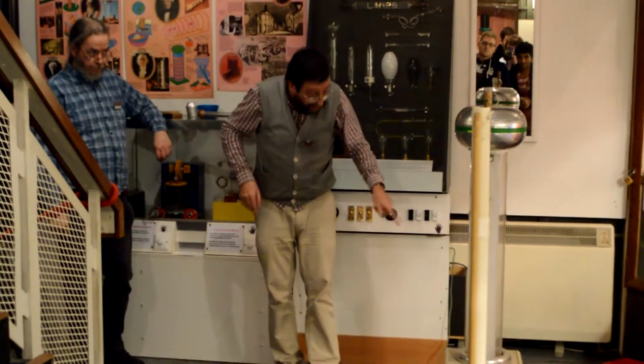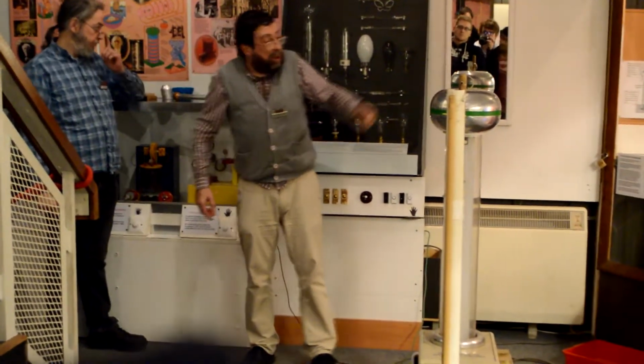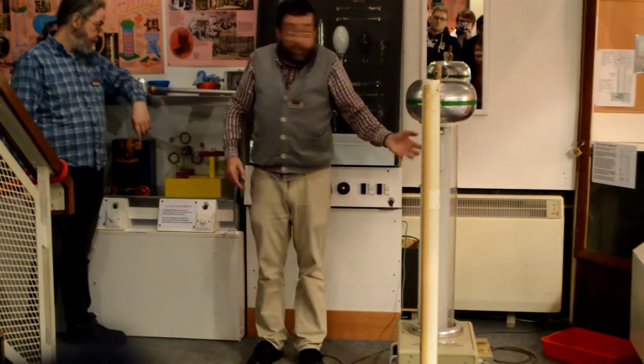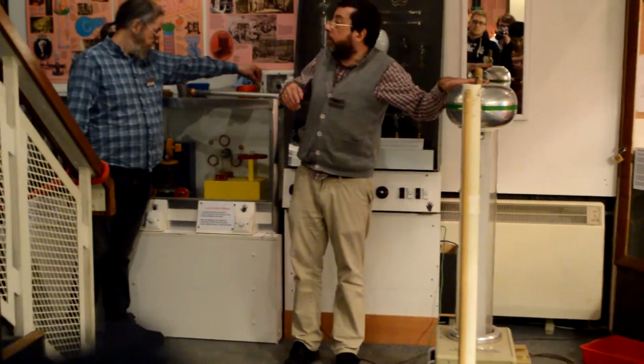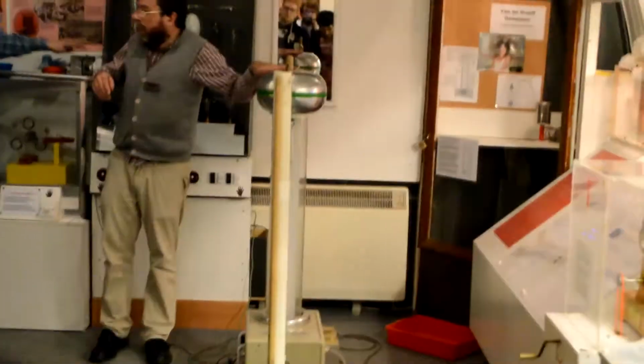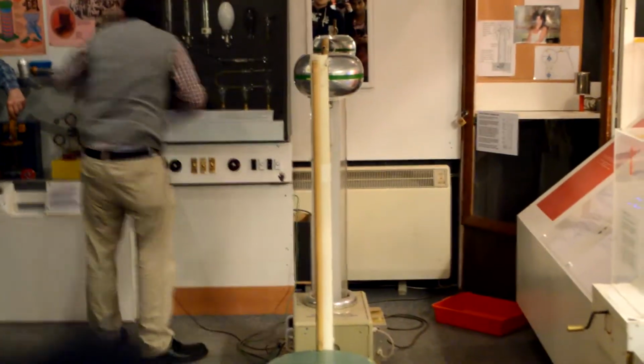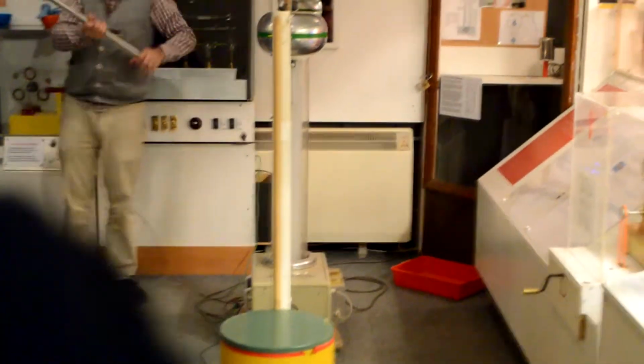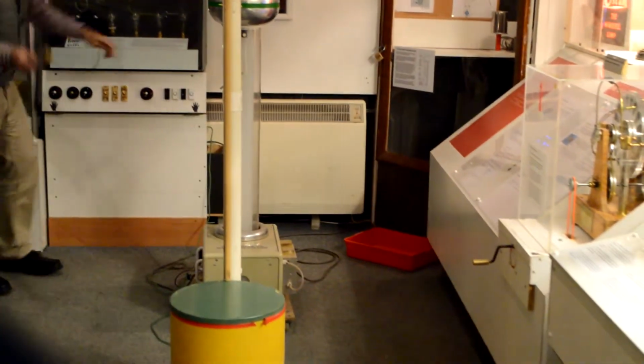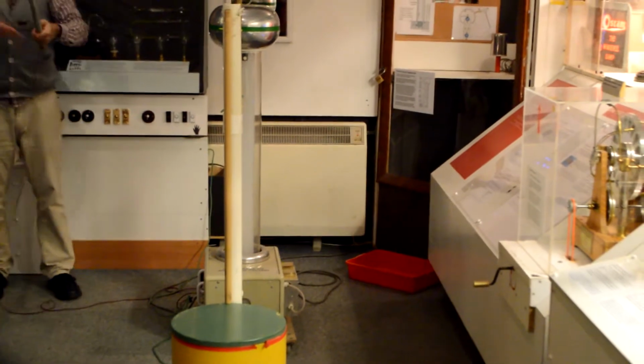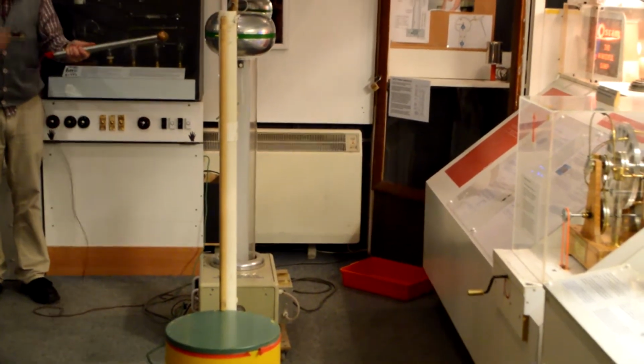If you just switch it on and press the HT circuit on, it will start accumulating charge onto this, in principle without limit, until something either leaks or flashes over. For that reason, whenever you operate things like this, the safest thing for the operator to do is to be earthed, and always have something at earth potential between it and you.